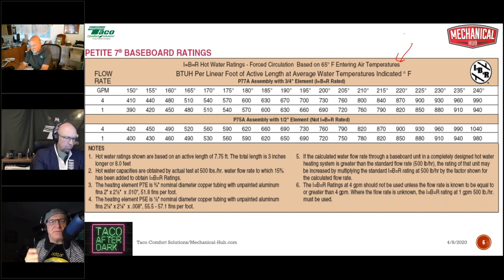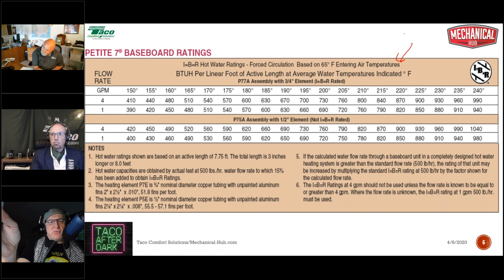Please take a look at the top portion of this chart. It's amazing the things you can learn by reading. This is the top line in this chart, IBR hot water ratings, forced circulation based on 65 degree air temperature. The second line is BTU per linear foot of active length at an average water temperature. So these numbers are average water temperatures. If we're talking about a 180 degree supply water temperature to that fin-tube baseboard, and we are designing it to the industry standard of 20 degrees worth of delta T, or a 20 degree temperature drop, the water is going out at 180, coming back at 160 for an average water temperature of 170. So we really need to be looking at that line and not that one, all right?